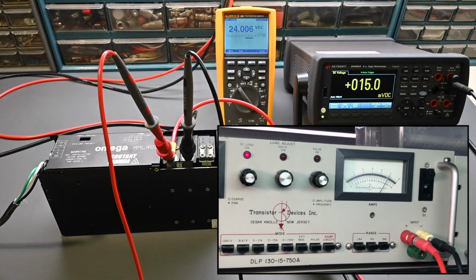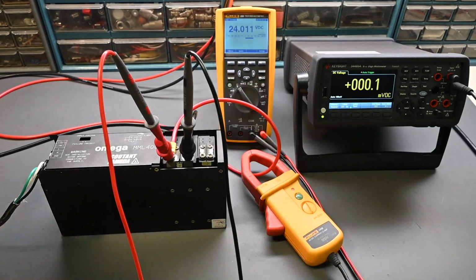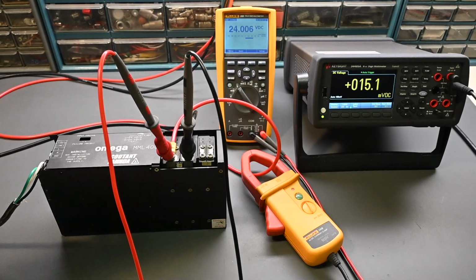So I'll switch the dyno load off and then back on. So when it goes off, the voltage holds pretty steady there. No major fluctuations or drifting or any problems. And I'll switch it back on. Right at 15 amps and no problem with the voltage. So that's looking very good, no issues whatsoever.